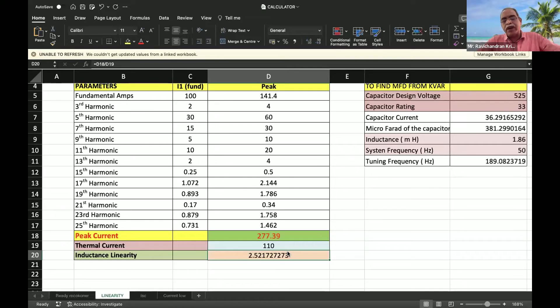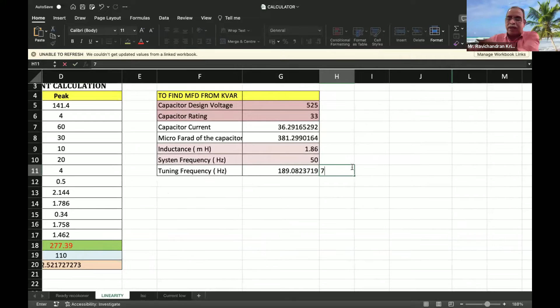In this location, if I use a reactor designed for linearity 1.8, then definitely the detuned filter and the entire system will fail. Or rather, it is not possible to immediately say that a passive filter is not worthy of installation. So the design is important. Just by seeing the detuning frequency and the 7%, no one should immediately use an off-the-shelf unit that is available.